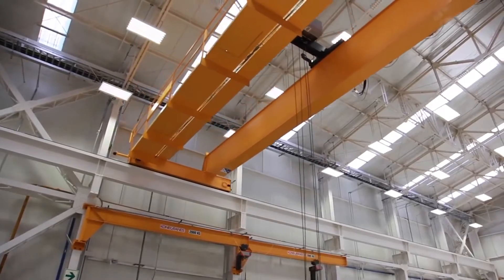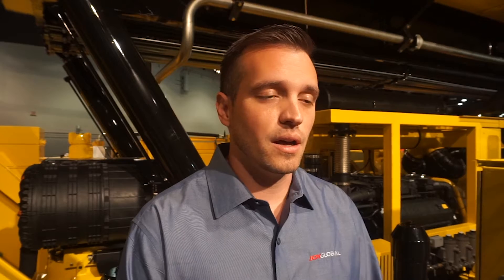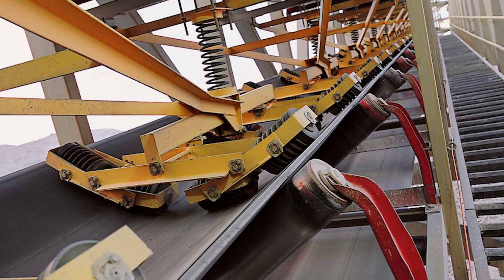One example of Joy Smart is in a Longwall application in Illinois. We utilized Joy Smart solutions to increase the availability of a system that often gets overlooked — the conveyor system. Initially during commissioning, I used benchmark recordings, meaning the start-up sequences, stopping, shutting down, and run-time, to understand the key deliverables and what paints a clean picture of normal conveyor operation.